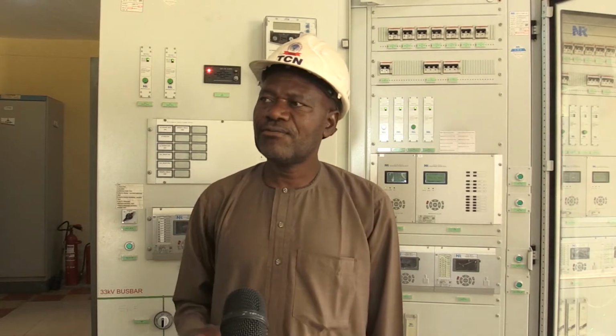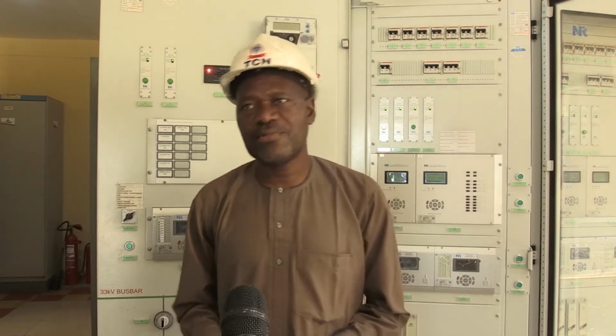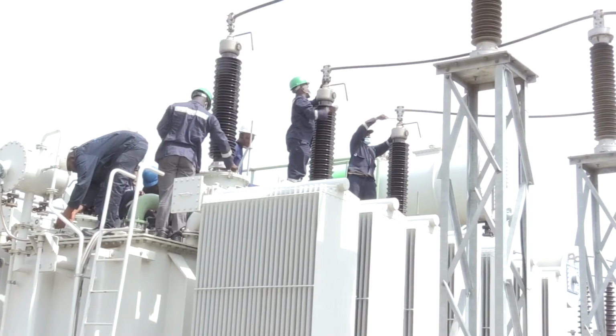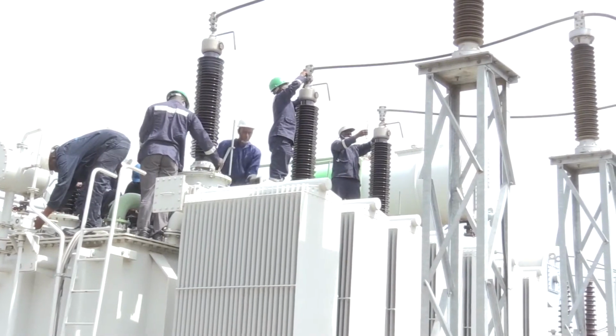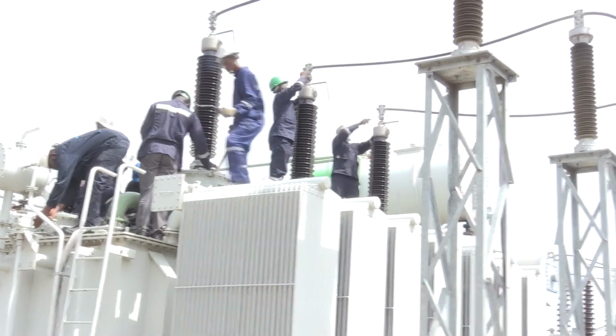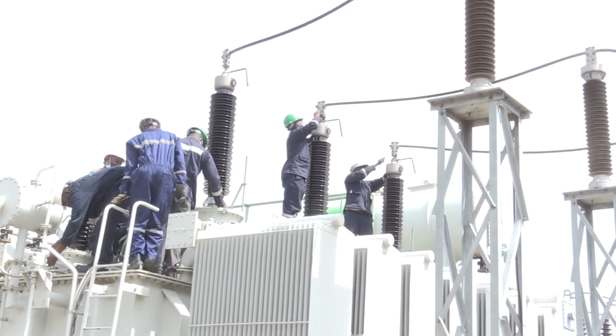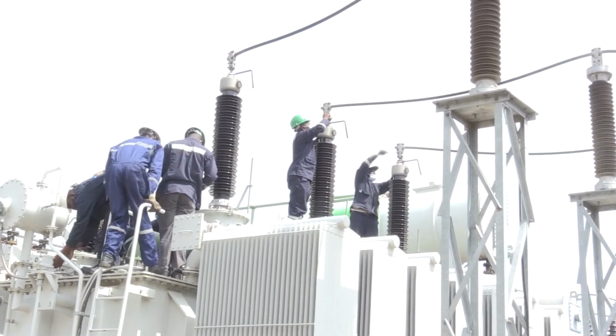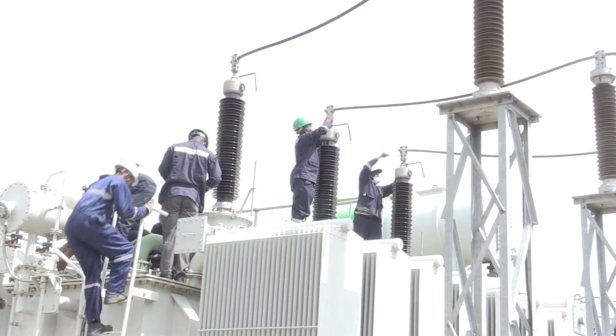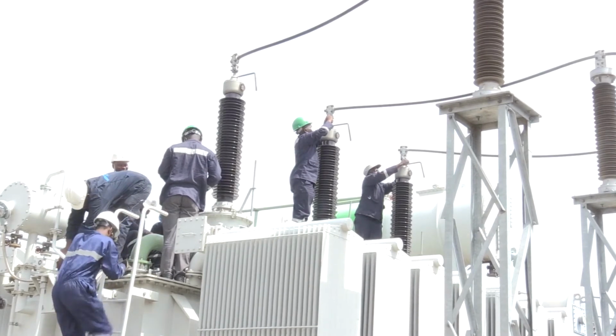The Assistant General Manager Transmission spoke about the procedures of the maintenance exercise and the units involved. We have linesmen here that will help us disconnect the whole transformer. When system operations disconnect the transformer by the breaker and so on, they hand it over to the maintenance people. A linesman first disconnects the overhead conductors, and then the main department, PCM and electrical, go up and check for leakages.